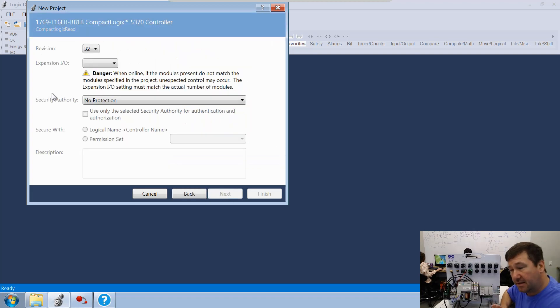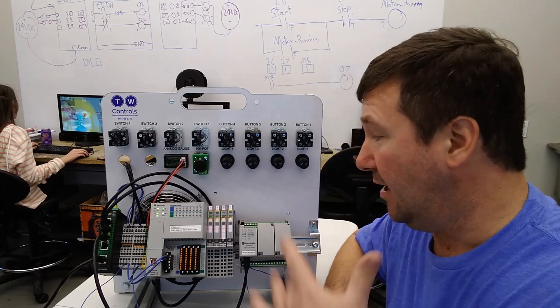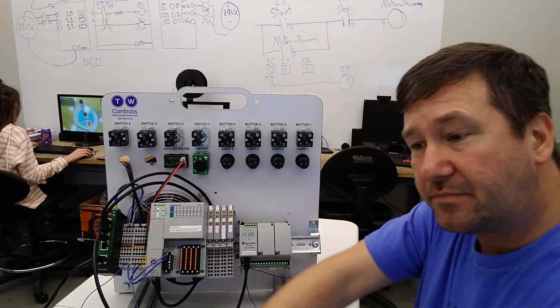If you're using one of our standard trainers, then the expansion IO needs set to zero. We've got some extra modules on here for some other videos we're doing, so we're going to use four here. It's very important that you get that part right, because otherwise your PLC is going to fault the moment you go to run mode.